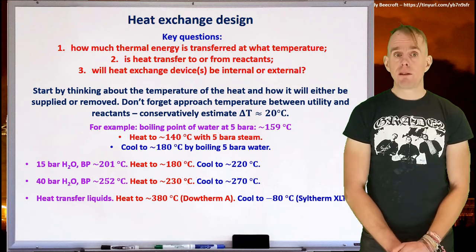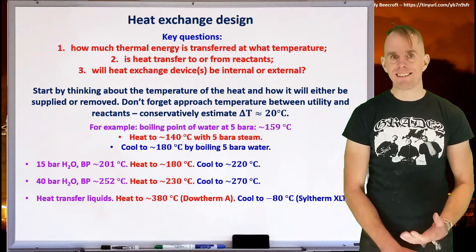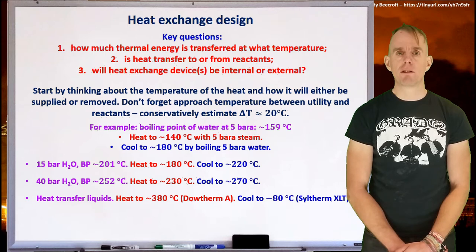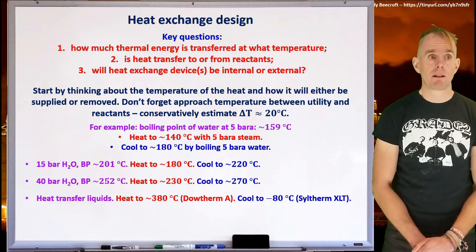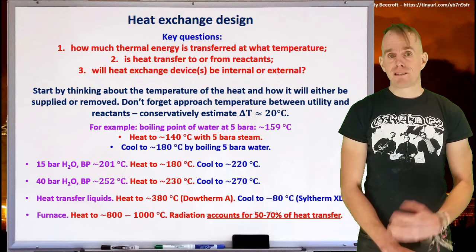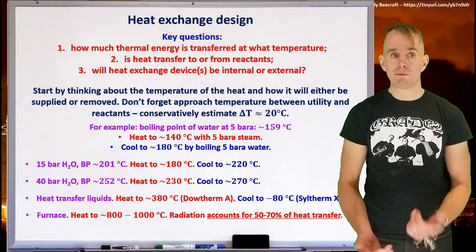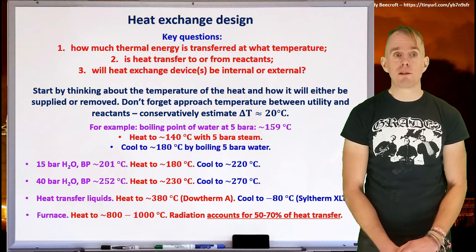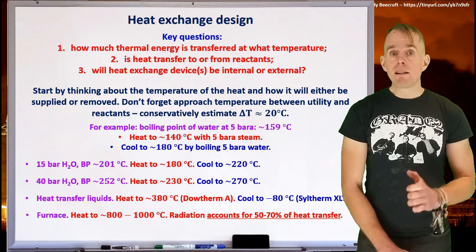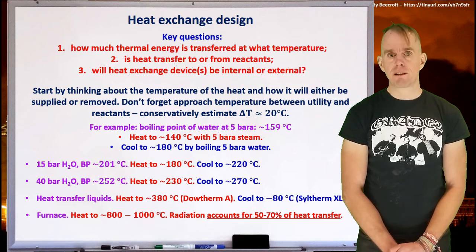As a cooling fluid, you can use Syltherm XLT, and that will allow you to cool to about minus 80, which is a lot lower than, say, some of the brine systems that you may commonly find. If you need to get heat at a higher temperature than around 380, 400 degrees C, then you have to go for a furnace. And so furnaces will allow you to heat up to maybe 1,000 degrees C. And radiative heat transfer accounts to probably up to 70% of the heat transfer that's used.